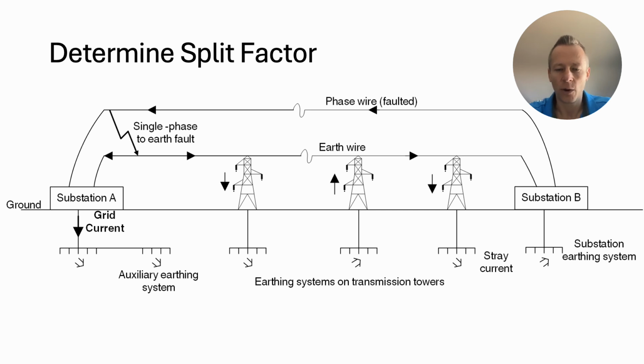So we need to come up with that max fault current and ultimately the split factor, which is how much goes into the grid. It turns out to be a function of the connections that you have: how many static wires, earth wires you have, what the impedance of their tower grounds are, how many distribution lines you have, what resistance you get on the pole grounds for those, and the resistance of the grid itself to earth. Basically those are all the parallel paths that the fault current can go on.